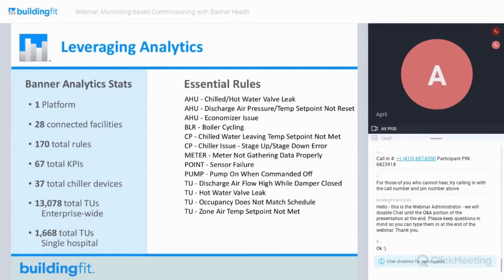Together with Banner, we've implemented a single analytic platform, so one place, one login, that unifies data across all 28 of their connected facilities. Data from the building automation system gets uploaded in real time and put through 170 different rules. I'll talk about some examples of these rules in a minute, but basically they are condition-based algorithms to detect fault within the system or equipment operation.